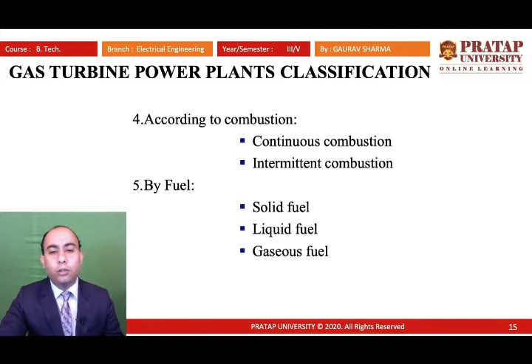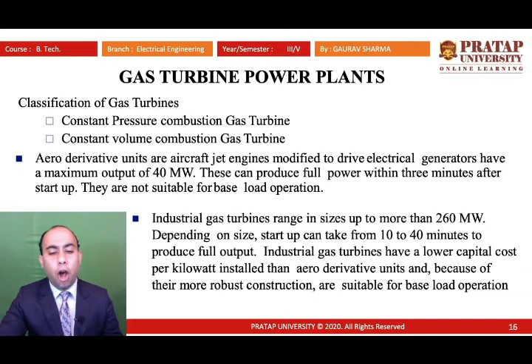Aeroderivative units are aircraft jet engines modified to drive an electrical generator, with a maximum output of 40 megawatts. These can produce full power within 3 minutes after startup. They are not suitable for base load operation. The aeroderivative units used in aircraft jet engines are also used for electric generation. Industrial gas turbines range in size up to more than 260 megawatts. As I already said, depending upon the size, they can take 10 to 40 minutes to give full output, and they are suitable for base load operation. They are robust in construction.